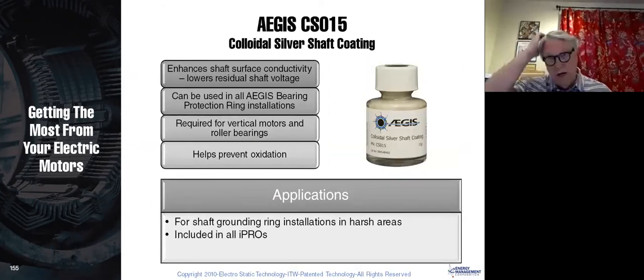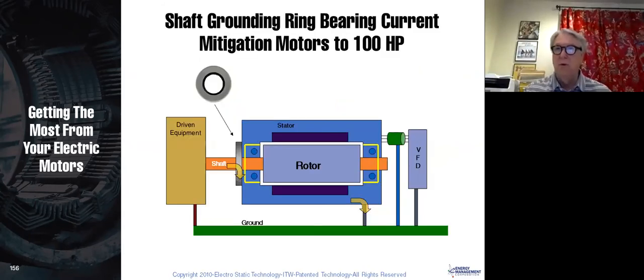It's also nice to have a colloidal silver shaft coating around the shaft in order to give that a lower resistance, make it really smooth. According to the bearing current manufacturers, that's the people that manufacture these grounding rings.